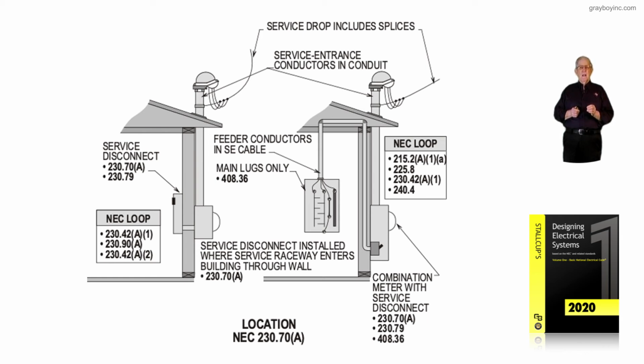If the overcurrent device is over 800 amps, we'd have to round it down. With that, we apply 240.91, and this facility is considered an industrial supervised location as defined in 240.90 and 92 of the NEC.